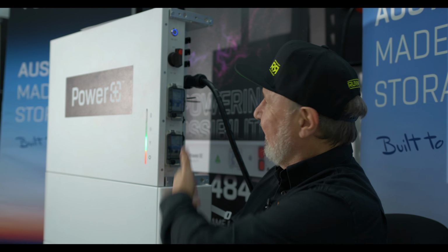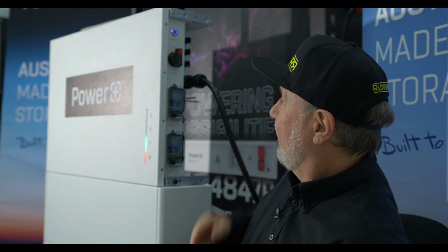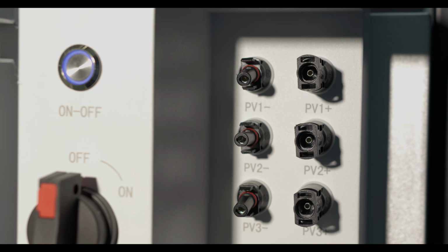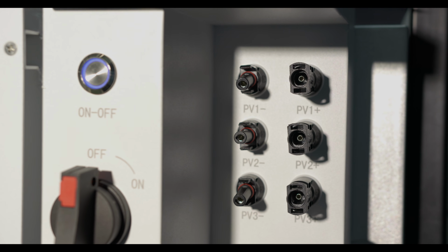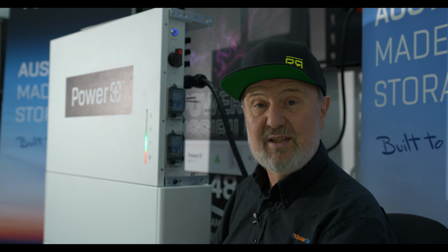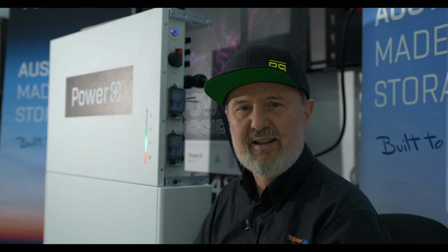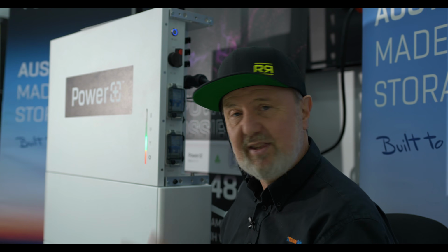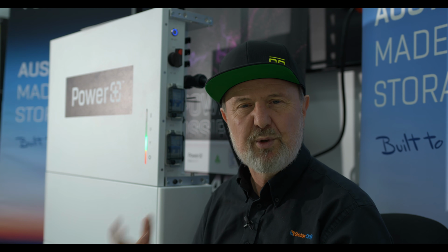So everything here is screened from touch and also from being damaged. We've got our connections for 3 MPPTs. They're rated at 3 kilowatts each, so you can overpower this unit. Overpowering is a really great idea with a hybrid inverter, something like this that's DC coupled. What do I mean by overpowering? Well, actually having more PV power than the inverter can convert.